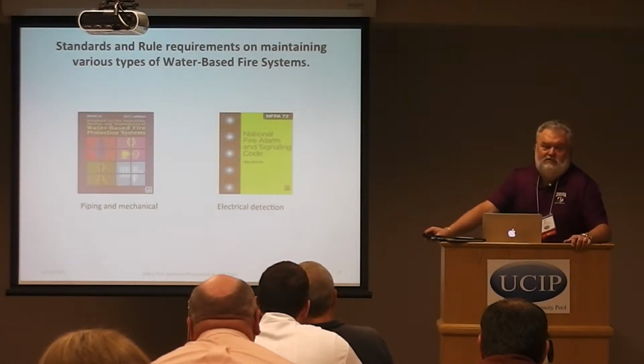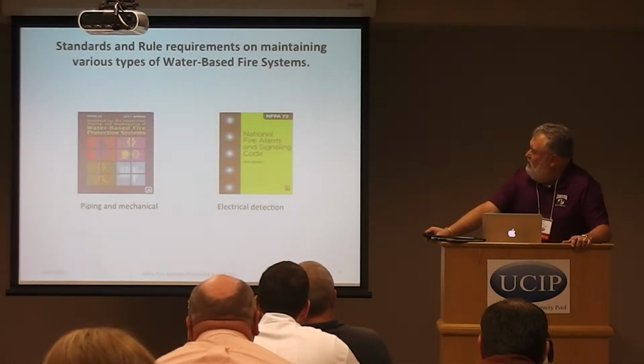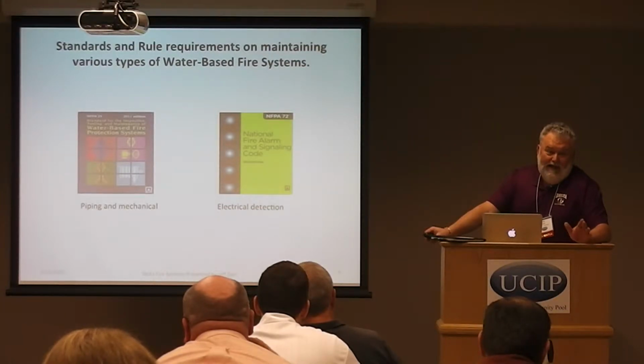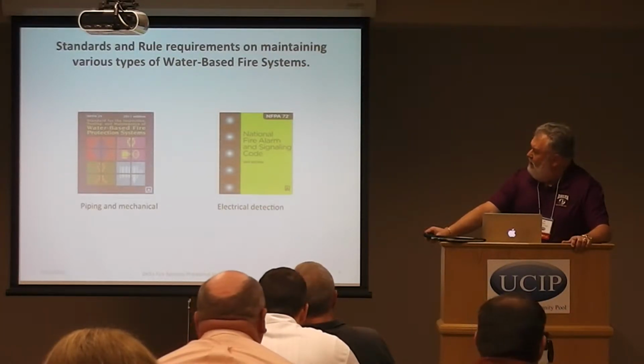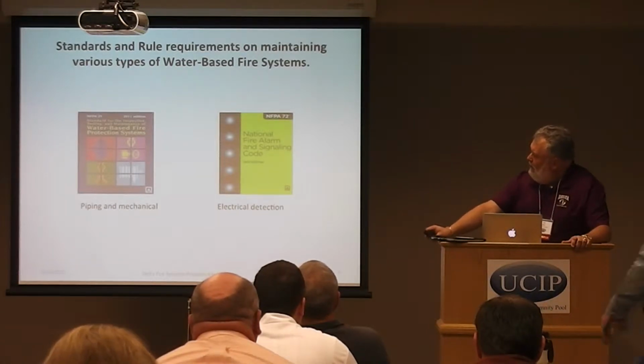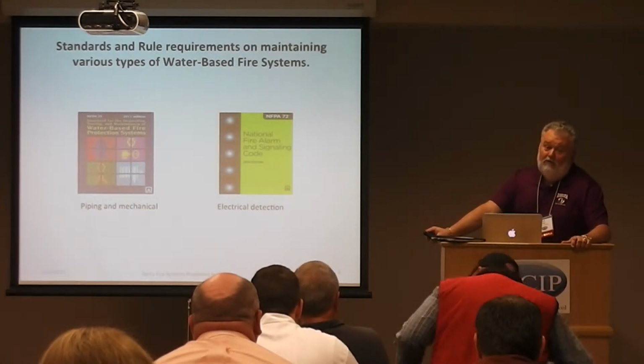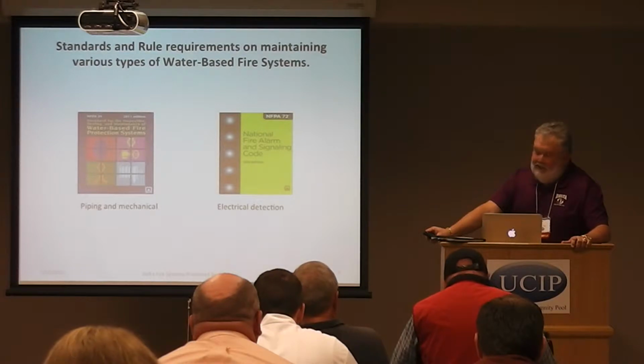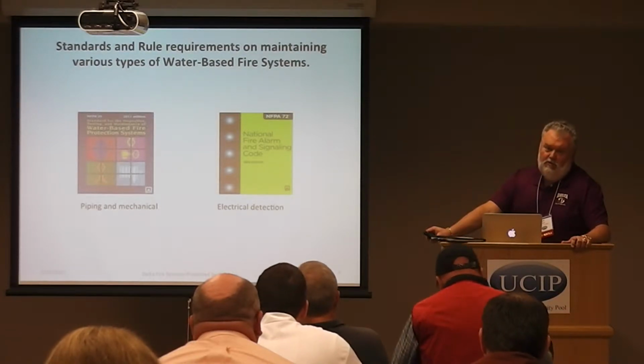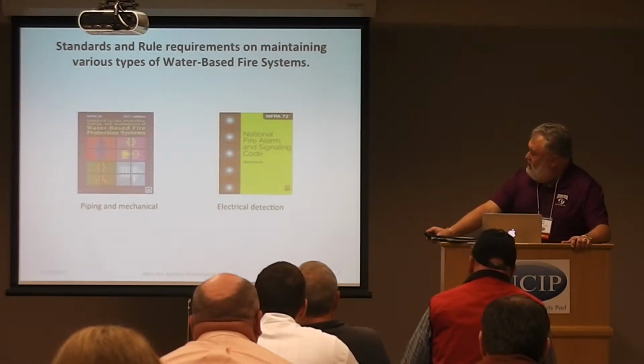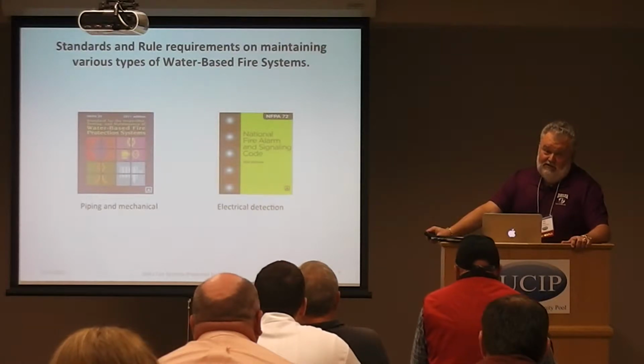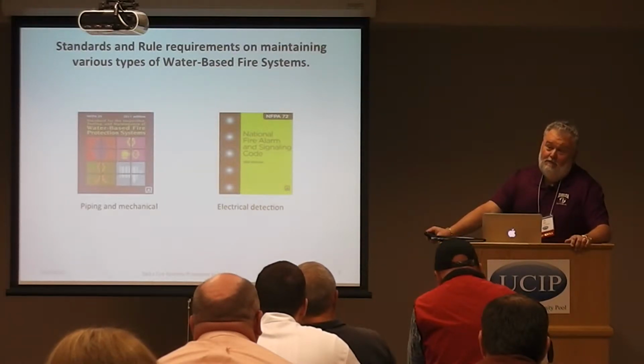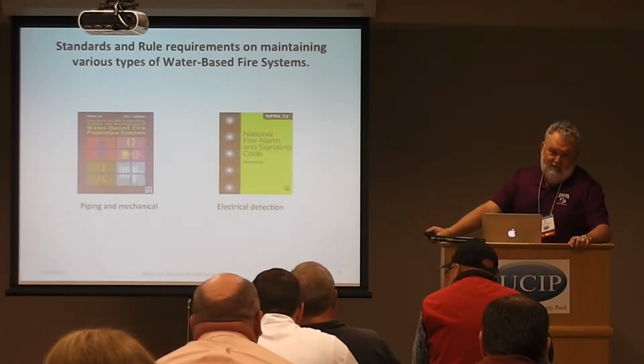Now, once they are installed, we have specific standards that we have to deal with on the inspection and maintenance. One of them for the piping, in any water-based system, is NFPA 25. The state is on the 2011 edition, but if you ask the state fire marshal, he thinks it's a 2008.